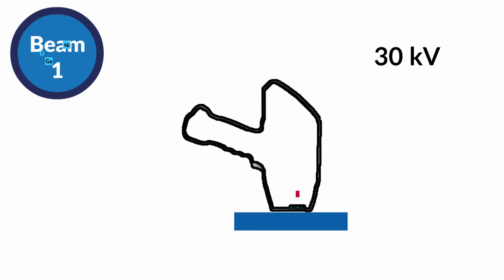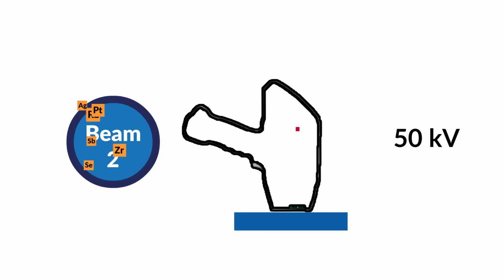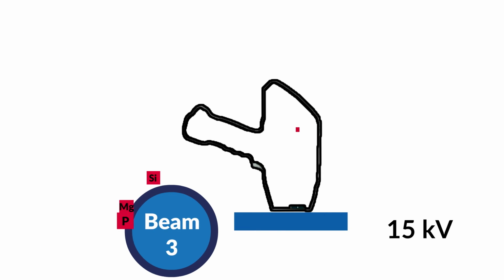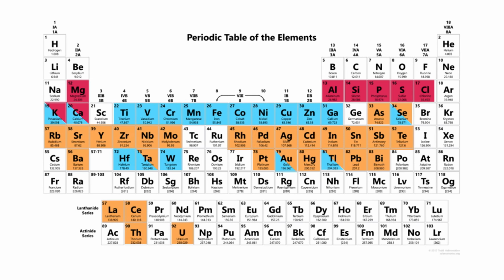When taking an analysis, there is more that goes on under the surface than just a single scan you can see. The calibration you are using may use 2 or 3 different phases to collect data for each scan. Beam phases are set on different ray intensities where the XRF excites specific elements. One beam will target light elements, another medium elements, and the other heavy elements.